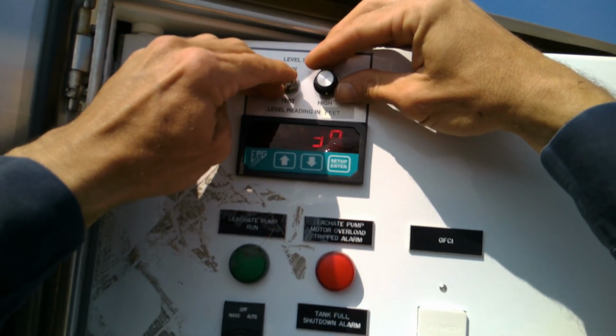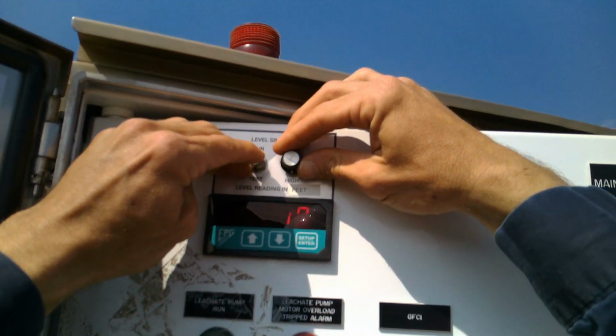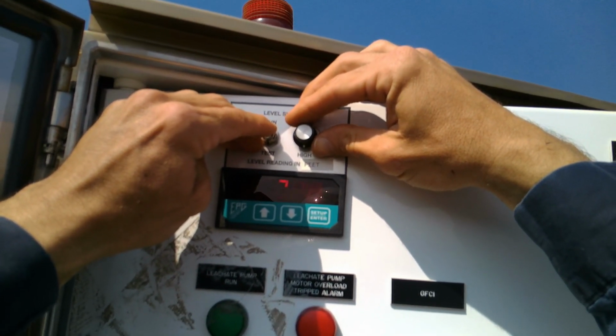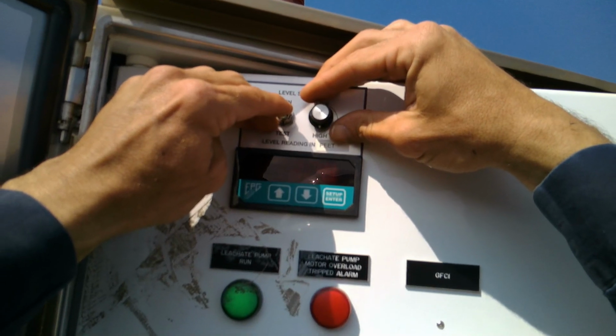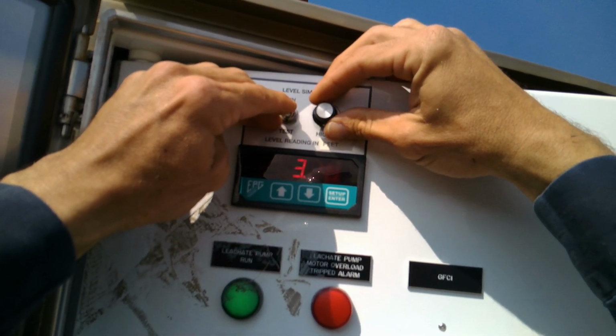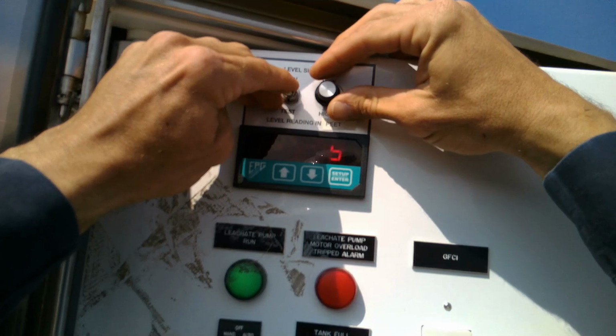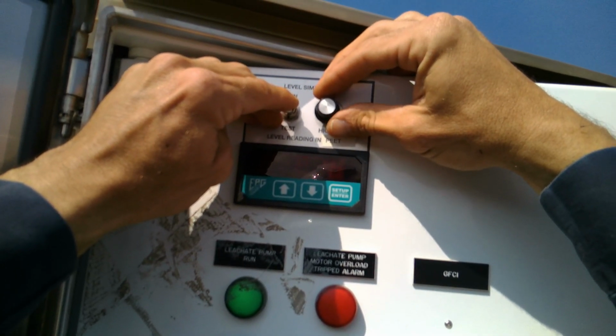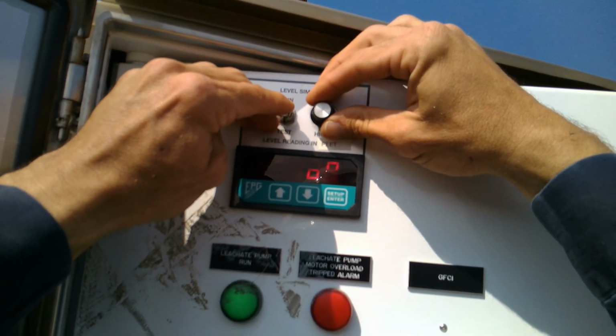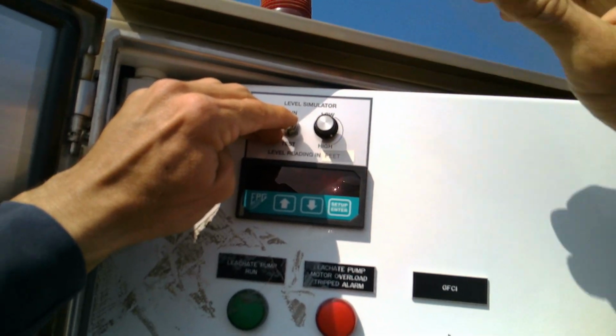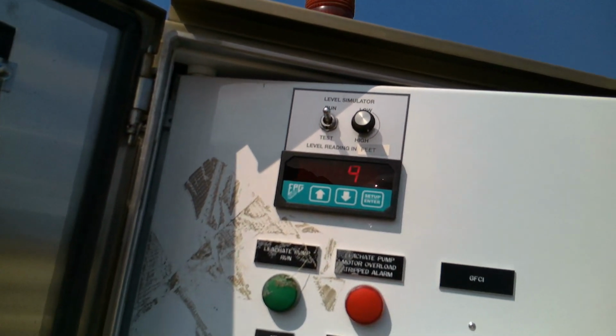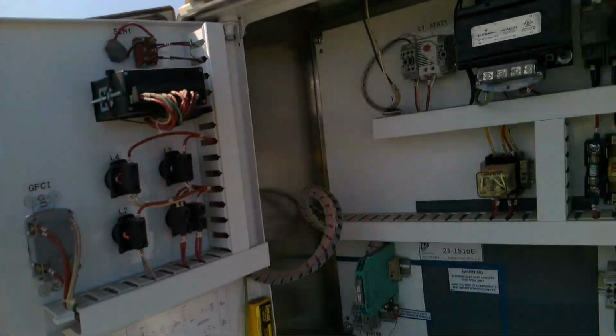2 feet, 2.2, slowly coming up. Boom, 3.11, 3.9, it comes on, and then it's going to stay on until it drops down to 1.41. 1.6, 1.5, and there. And then we'll take it out of test mode. So there you go. This sump is also working in automatic.